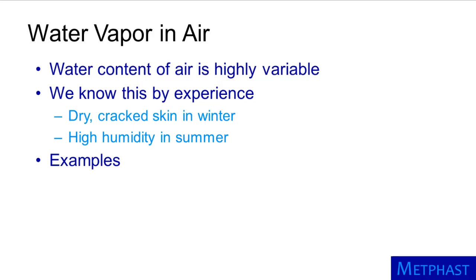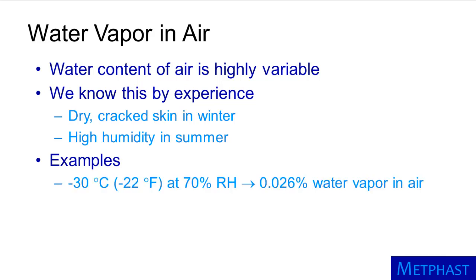Let's take a look at some examples of the amount of water vapor in the air on a percentage basis in some different atmospheric conditions. Our first set of conditions is a temperature of minus 30 degrees Celsius (minus 22 degrees Fahrenheit) at 70% relative humidity. Relative humidity is the amount of water vapor present in air expressed as a percent of the amount that would saturate the air — the point at which dew would begin to form — at the same temperature. So, at minus 30 degrees Celsius and 70% relative humidity, water vapor would make up less than 0.03% of the air. This is less than the amount of carbon dioxide that would be present. This situation occurs regularly in northern Minnesota, for example, during the middle of winter.